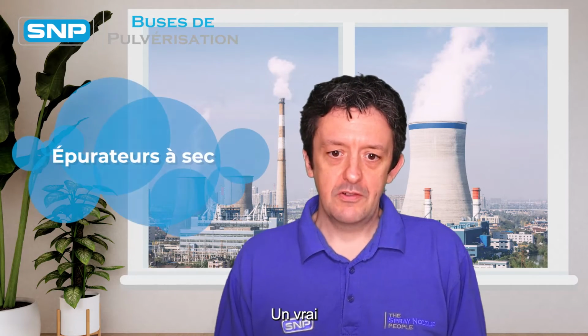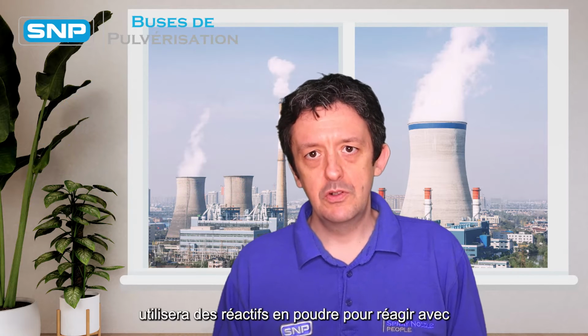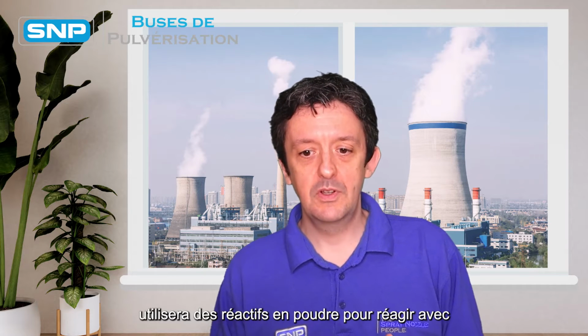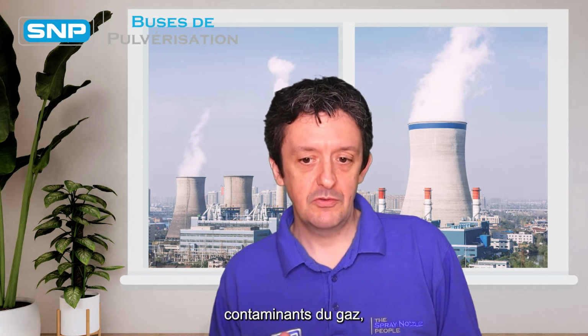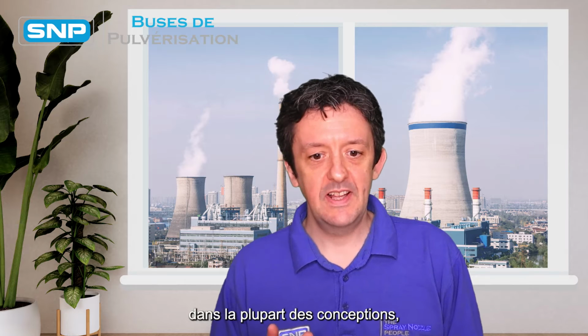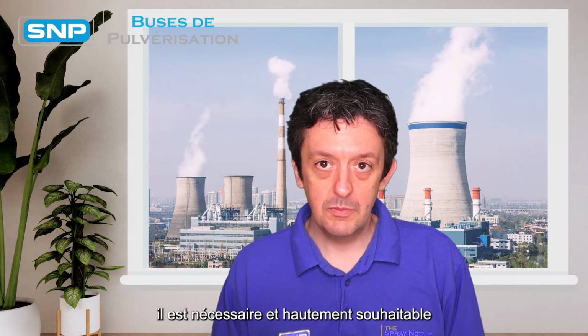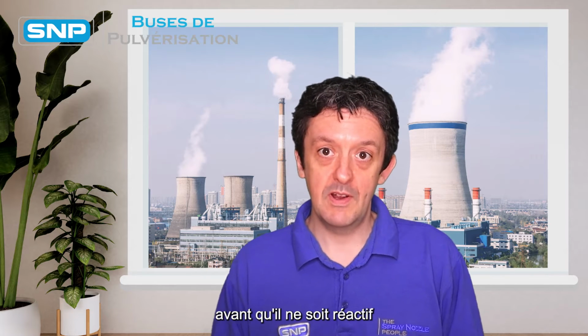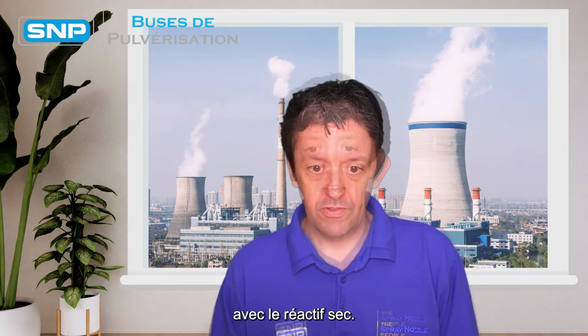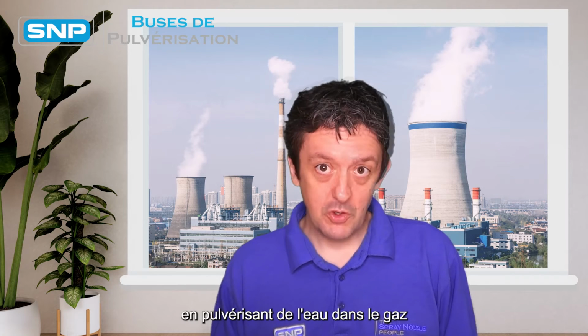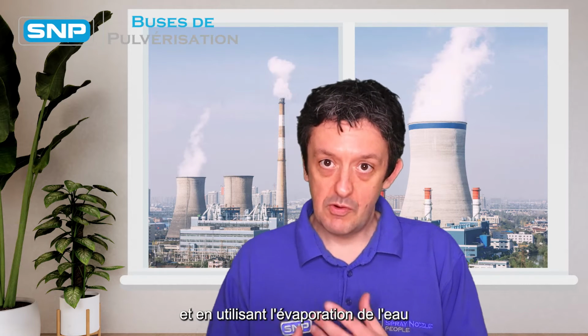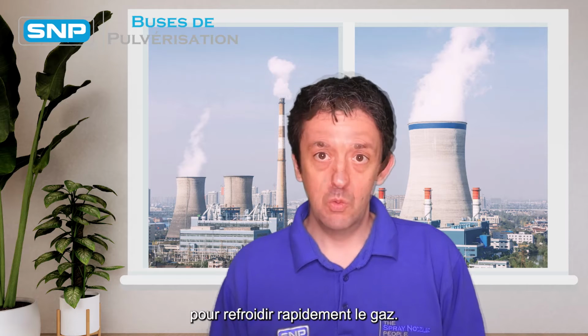Now, a true dry scrubber will use powdered reagents to react with the contaminants and remove contaminants from the gas, and so does not require spray nozzles to spray the reagent into the gas flow. However, in most designs it is necessary and highly desirable to pre-cool the gas before it is reacted with the dry reagents, and this is normally achieved by spraying water into the gas and using the evaporation of the water to rapidly cool the gas.